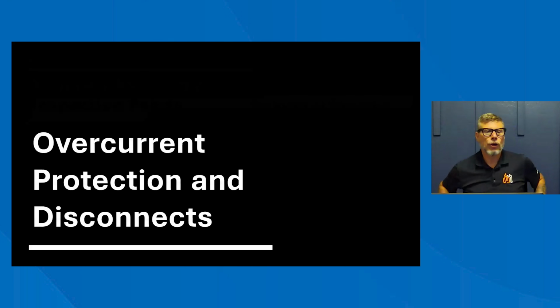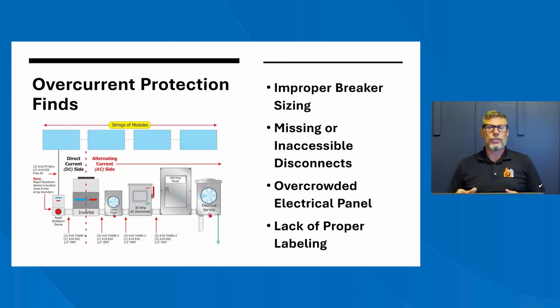So let's talk about our overcurrent protection and disconnects. These are pretty important. If you talk to any electrician, they're going to tell you that this is a very redundant system with all of the disconnects. You've got 3 common disconnects. You have your DC disconnect. The power comes in from the array, hits a DC disconnect, then goes to your inverter. From the inverter, it goes out to your net metering, then it has a disconnect, and then it goes to your service panel.